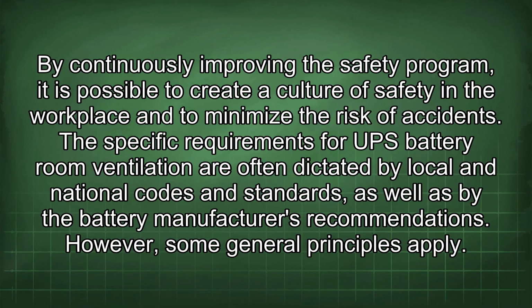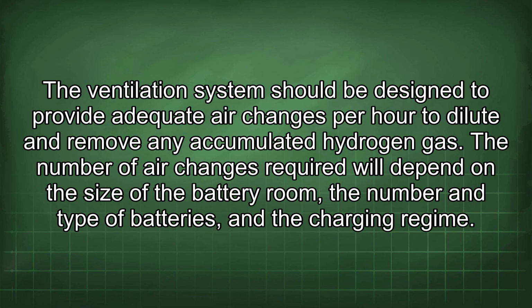The specific requirements for UPS battery room ventilation are often dictated by local and national codes and standards, as well as by the battery manufacturer's recommendations. However, some general principles apply. The ventilation system should be designed to provide adequate air changes per hour to dilute and remove any accumulated hydrogen gas. The number of air changes required will depend on the size of the battery room, the number and type of batteries, and the charging regime.